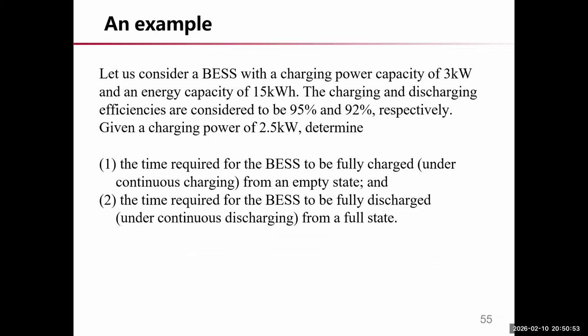Here's an example of charging and discharging power: a BESS with charging power capacity of 3 kilowatts and energy capacity of 15 kilowatt-hours, with charging and discharging efficiency of 95% and 92%. Given a charging power of 2.5 kilowatts, we can calculate the time required for the BESS to fully charge from an empty state, and the time required for it to fully discharge from a full state.